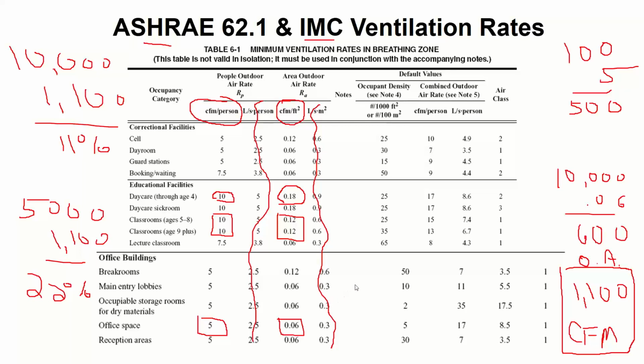And I think I answered Mike's question inadvertently. What if the building is unoccupied, the OA damper closed? The OA damper should close when the building's unoccupied. I will tell you that more than 80% of buildings don't do that because they don't even know that. Now, if you have a building automation system, a computer-based network system, you're probably doing that. If you have regular thermostats on the wall, you 100% for certain are not doing that because it requires a special thermostat that costs $10 more than the other stats.